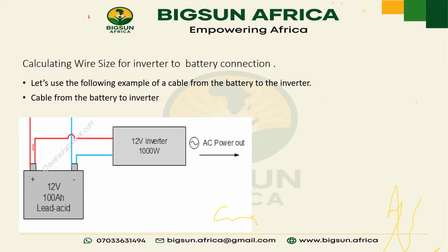520 amps, right? Yes. Okay. So applying our formula, we have 520 amps times 9 feet, all over our voltage, which is 12 times 2.